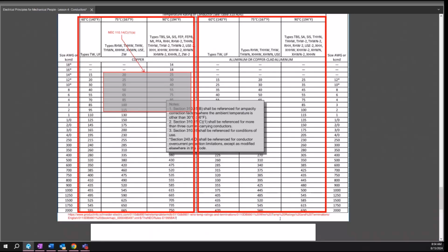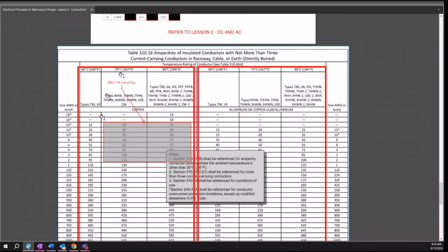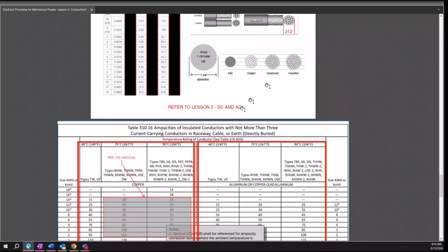The last thing I wanted to talk about is the different tables for this stuff. So this is table 310.16. And this is specifically for not more than 3 current carrying conductors in a raceway, cable, or direct buried. So essentially, if you've got 3 normally current carrying conductors, which are phase A, B, and C, the neutral doesn't count, ground doesn't count, and you're in a raceway, which is essentially a conduit, you're in a cable, or you're directly buried in the ground, this is your ampacity. The reason for that is that the raceway, the earth, is basically an insulator. So as you have heating on that conductor, it's going to hold in and retain that heat.